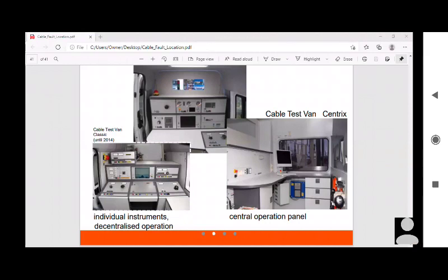See, whenever you use it, yes, your healthy signature will come, because you need to know the length of the cable. So what you do is, if it's a high resistance fault, you send a pulse. The pulse will travel through till the end, because when you find a fault, you have to disconnect the cable from both ends. So the complete length trace you will get.